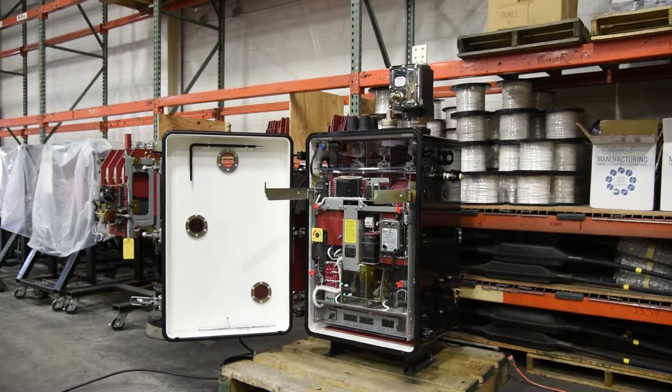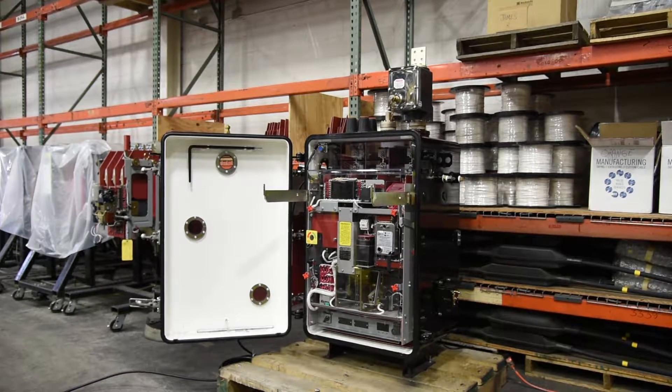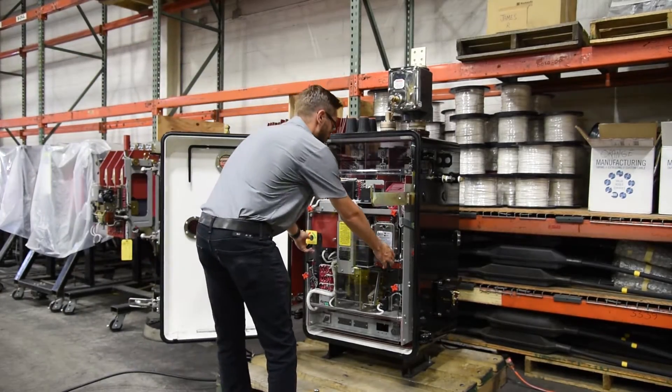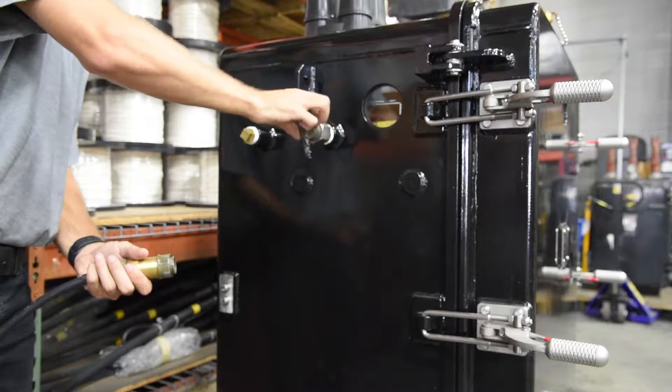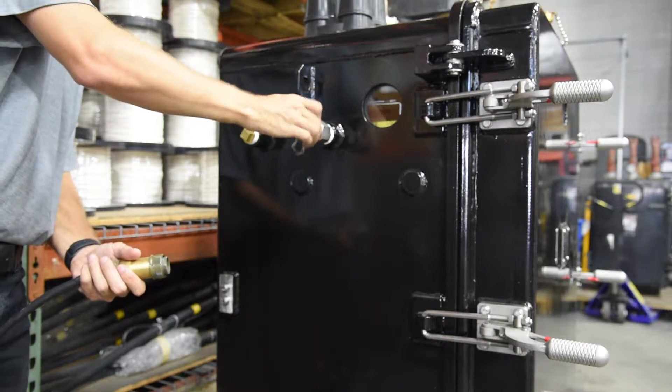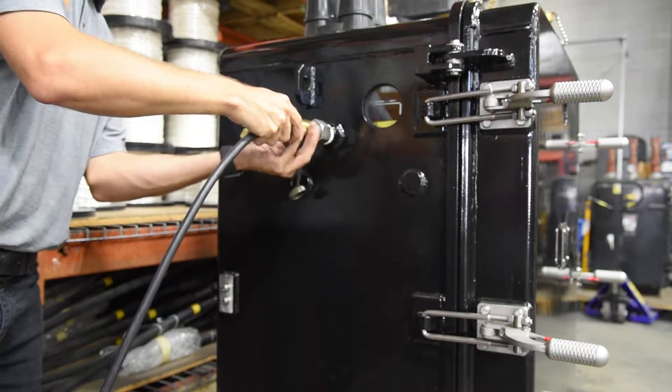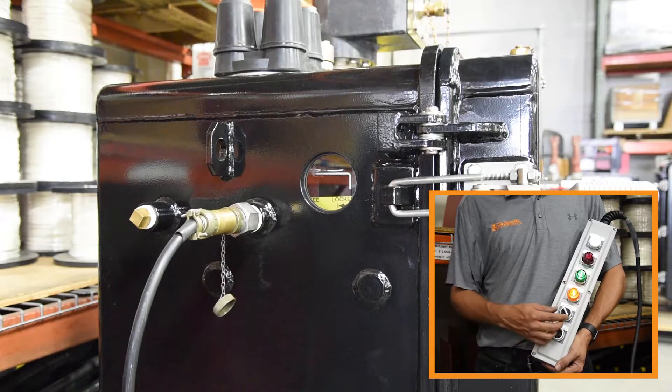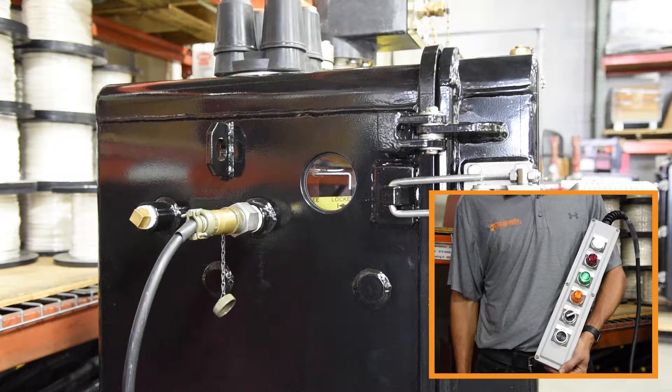One of the most exciting features of the 416NP is the motorized racking system. The motorized racking system engages and disengages the mechanism from the enclosure bus bars. The racking system is controlled with a racking pendant which mates to a bulkhead feed through on the side wall of the enclosure. The racking pendant allows the user to stand as far away from the unit as preferred, even outside the vault.